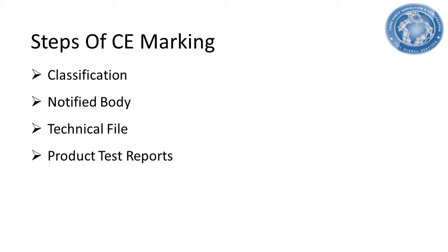You have to get the product tested in an independent test laboratory. Preferably, it should be an ISO 17025 accredited test laboratory, and you have to collect the successful test reports of your product. You have to evaluate your product for its safety and effectiveness by referring to European guidelines for clinical evaluation, which include steps starting from literature citation and also clinical evidences.